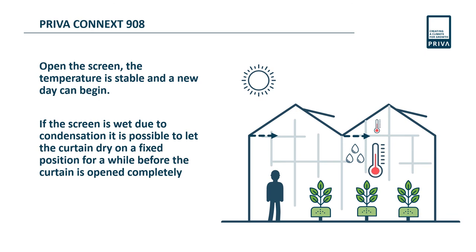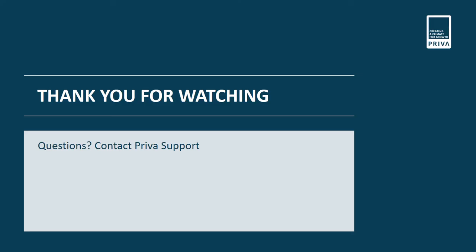If the temperature above the screen is high enough, we can open the screen without having any effect on the greenhouse temperature. If the screen is wet due to condensation, it is possible to let the curtain dry on a fixed position for a while before the curtain is opened completely.